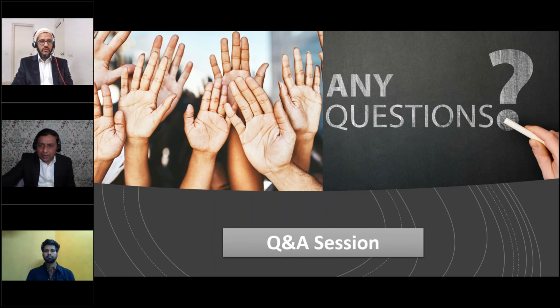Maybe one more, Kuldeep. Yeah, please go ahead. Maybe you can add, if this is just an app and there's no physical device, the app itself, nowadays depending on what it is doing, for example an app on your iPhone, is sometimes considered a medical device. So for that you'll have to follow all those requirements, if I'm not wrong. No, you're absolutely correct. Initially, a couple of years ago, it was very challenging for folks to understand that your app can also be a medical device, and you need to follow IEC 62304.